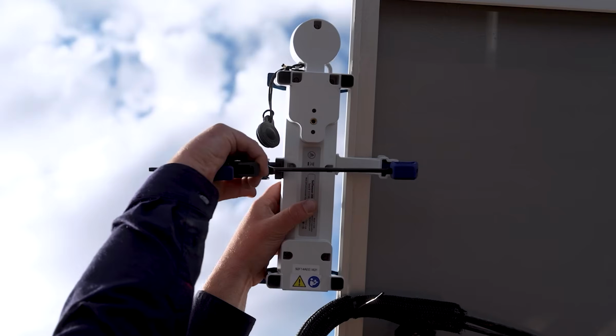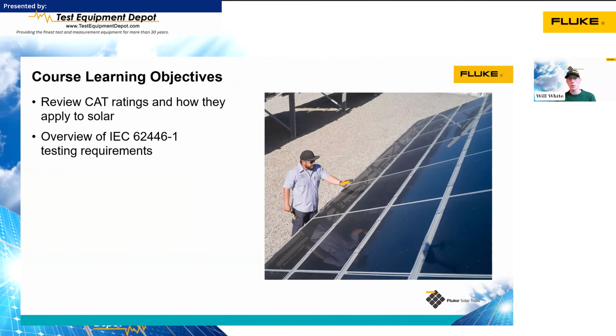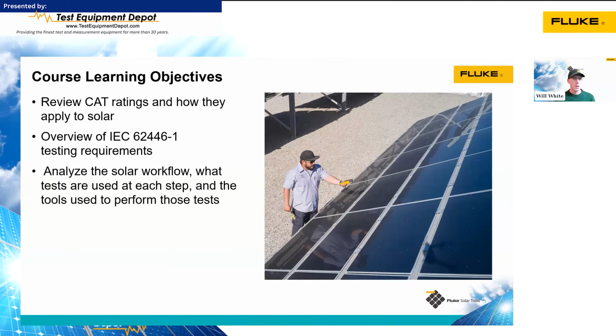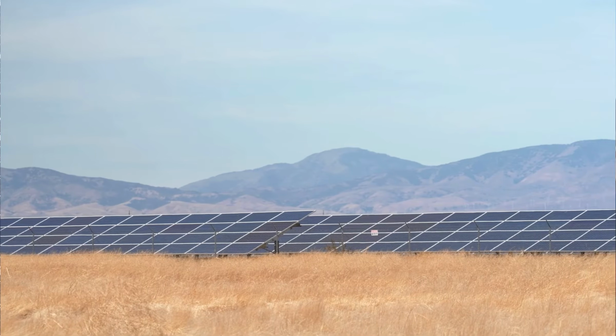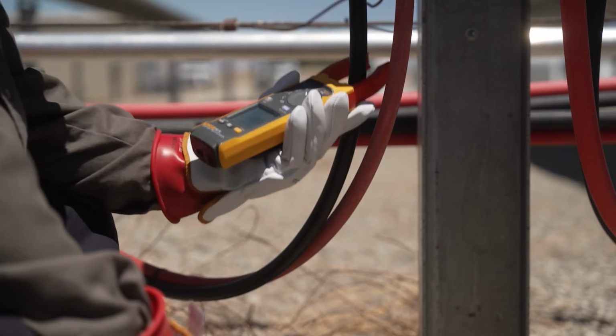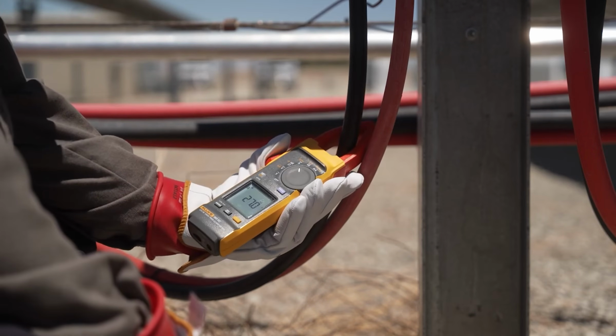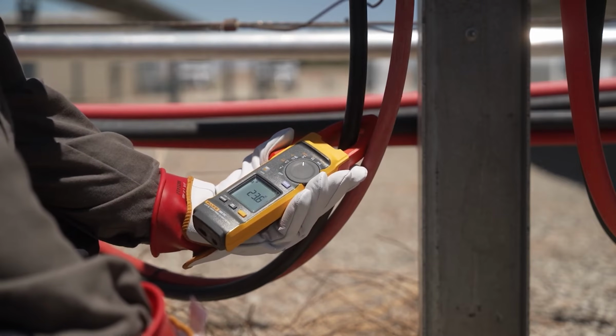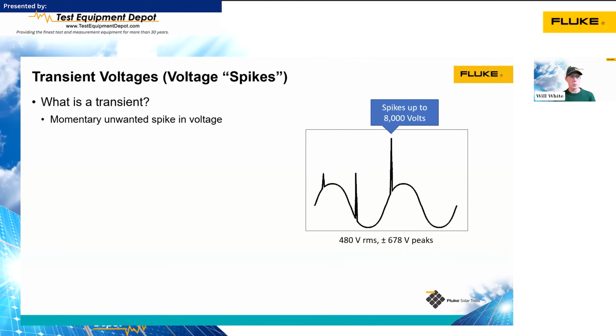We're going to talk about IEC 62446-1, which is a standard for testing grid-connected photovoltaic systems. That's a standard that's a requirement in many European countries and is a good guideline for testing our systems here in the United States. And finally, the bulk of the presentation will be going through the solar workflow, looking at all the tests that are done when we're working on solar, from installation through commissioning and then into operations and maintenance. So the first thing we need to know is what's a transient voltage spike?